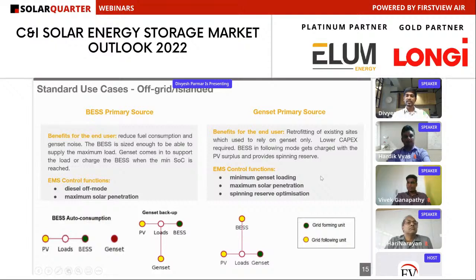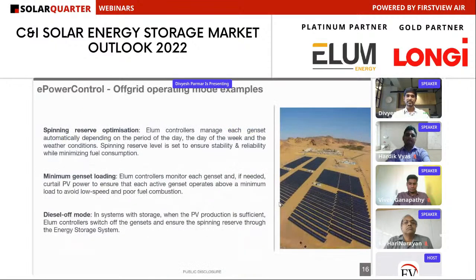And when you are dealing with, for example, say brownfield projects where already you have a big size of gensets, then you can install or incorporate an additional small battery system into your power plant, and you can do the functions like the minimum genset loading, solar maximization, as well as the spinning reserve optimization. So in the next slide, I will discuss the spinning reserve. So these are some of the operating modes for the off-grid power plant.